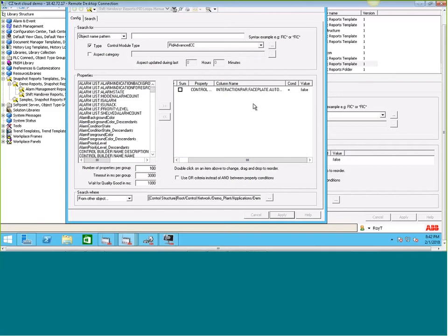In this case, whatever object you're looking at, some libraries say that it's true. It might be a manual mode, a separate parameter called manual mode, and you want to look for that to be true. Some have one that's auto and it's either true or false. So you just have to know your library a little bit to know what you're going to do there.